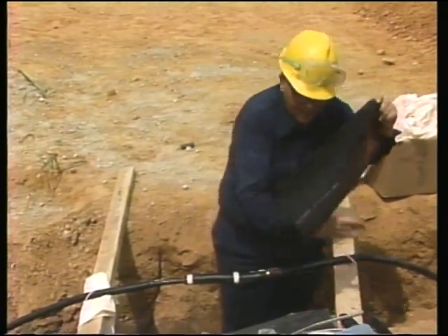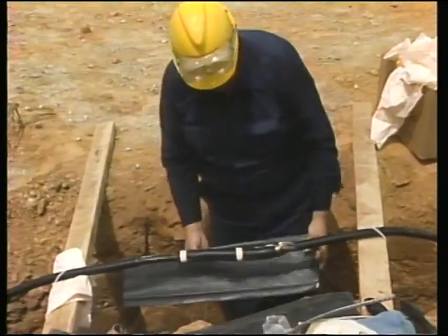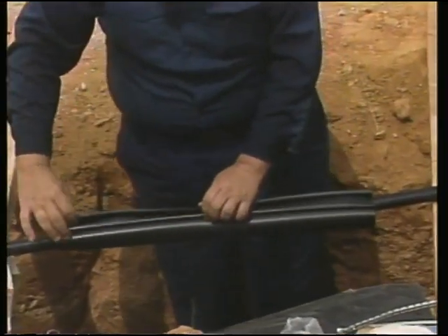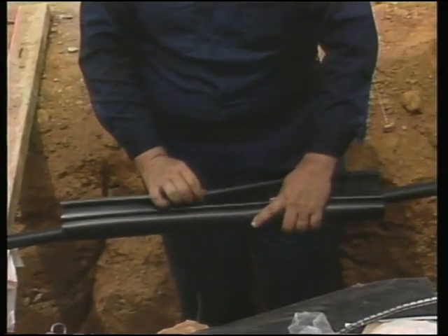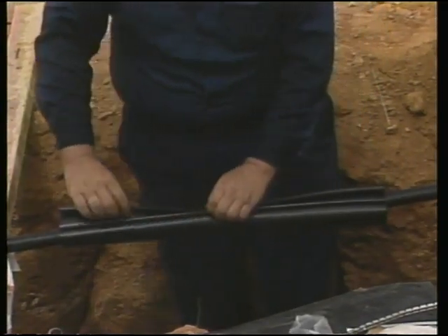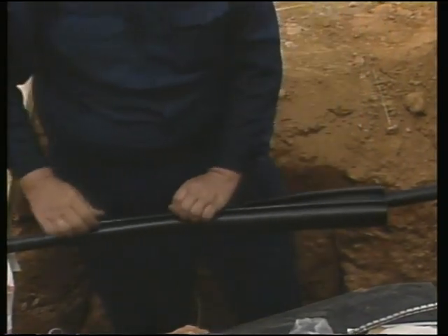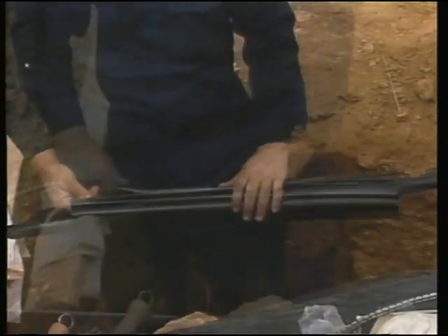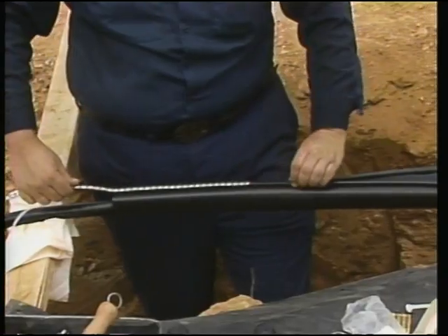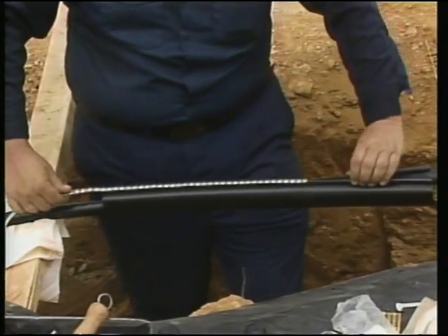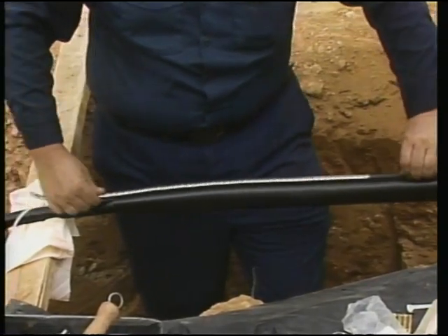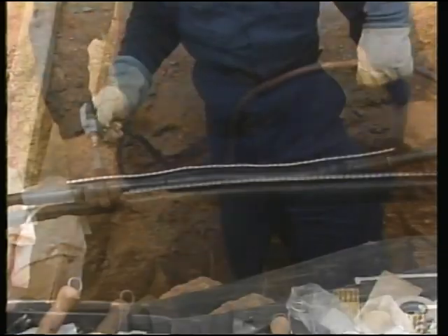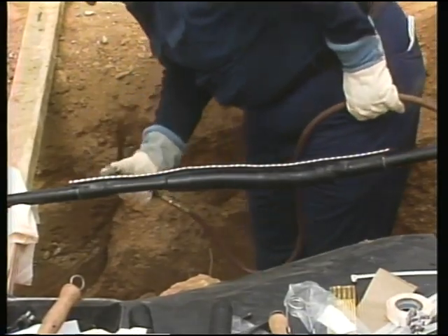If the cable originally had a jacket, as this one did, an additional tube may be applied over the splice tubes and over the concentric wires to provide the protective properties of the jacket. This additional tube is applied just as the others were. Or, as we see here, it may be a jacket like this, designed to wrap around the cable and be secured with a zipper-like metal clip before it is shrunk down.